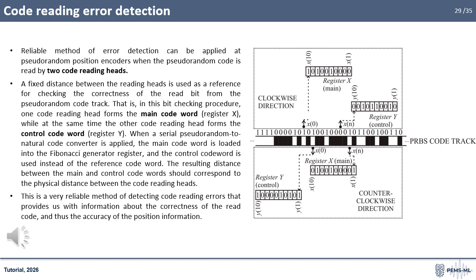When a serial pseudo-random to natural code converter is applied, the main code word is loaded into the Fibonacci generator register, and the control code word is used instead of the reference code word. The resulting distance between the main and control code words should correspond to the physical distance between the code reading heads. This is a very reliable method of detecting code reading errors that provides us with information about the correctness of the read code and thus the accuracy of the position information.